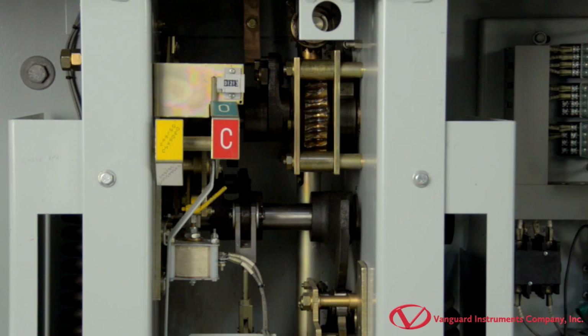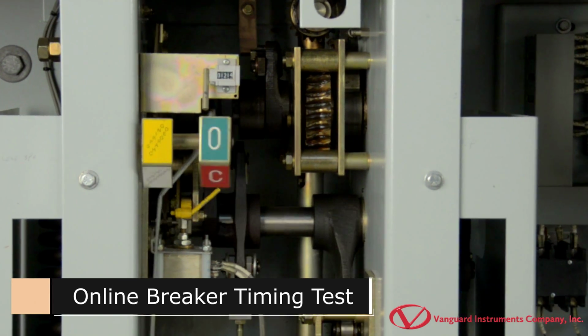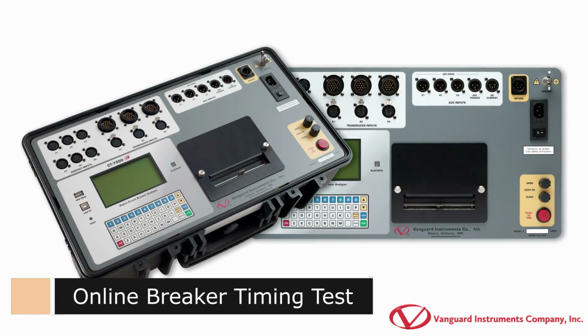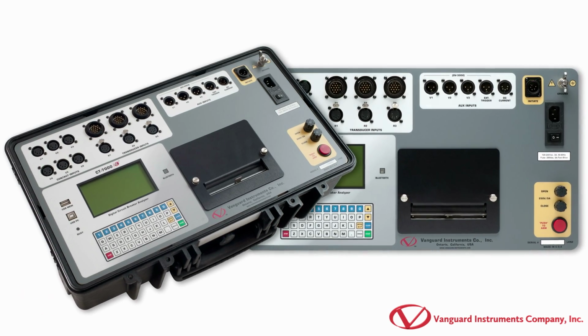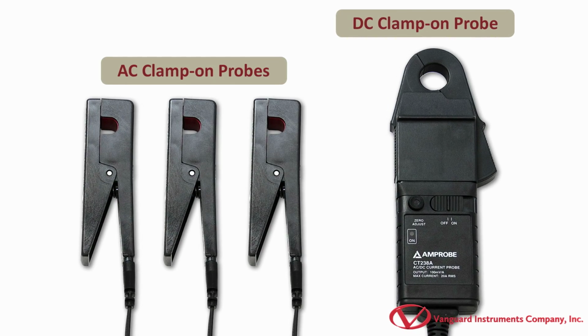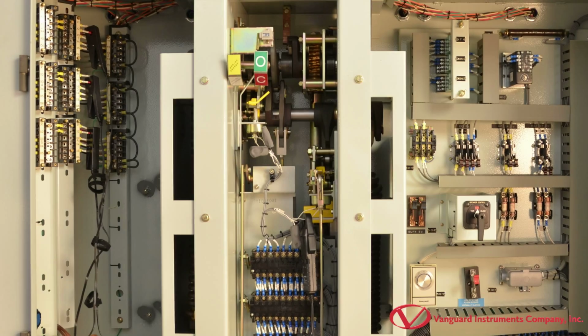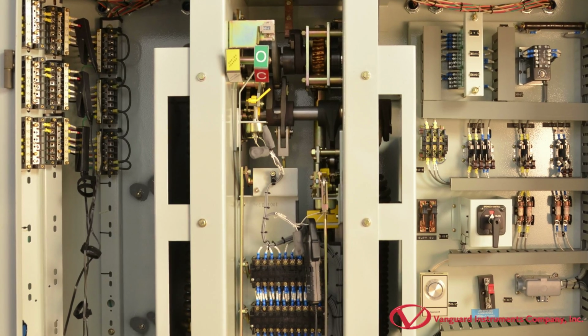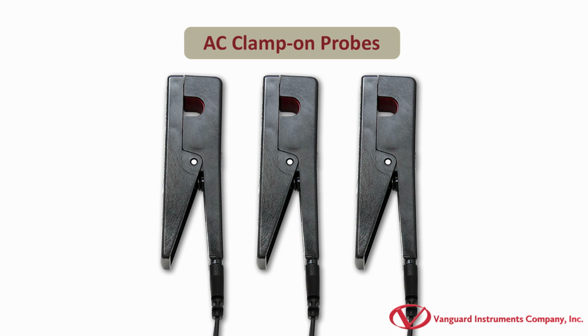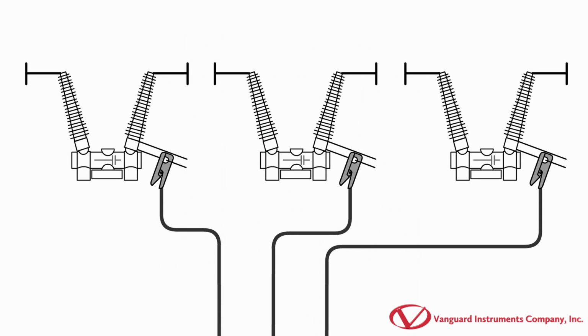In this section, we will go over the steps to perform an online timing test with the CT-7000 S3's online timing option. The online timing option enables the CT-7000 S3 to conduct timing tests while the circuit breaker is still in service.